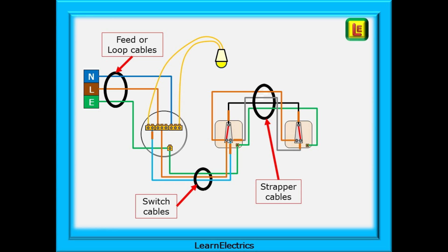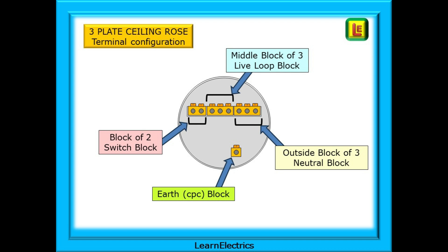Notice the brown sleeving on the conductors that might become energized to 230 volts at certain times. It's important to follow the standard convention for terminal configuration at the ceiling rose. Anyone following behind you will then know which wire is which. The ceiling rose has three brass blocks. One with two terminal holes and two with three holes. The block of two is always the switched line. In normal operation it will sometimes be at 230 volts and sometimes at zero volts depending on the switch positions, lights on or lights off. The middle block of three is always the live loop block. This block is permanently energized regardless of the switch settings. And the outside block of three is the neutral block. Finally there is an earth or CPC terminal.